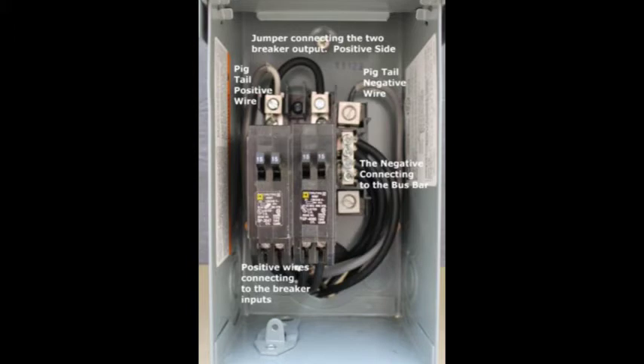Here you can see at the top of the combiner box the jumper that goes from the positive on the first twin breaker set over to the positive on the second twin breaker set. This combines the four positive outputs to the charge controller. You can see on the left the positive pigtail connection, on the right the negative pigtail connection, and also on the right the negative bus bar where all four panels terminate their negative cables.